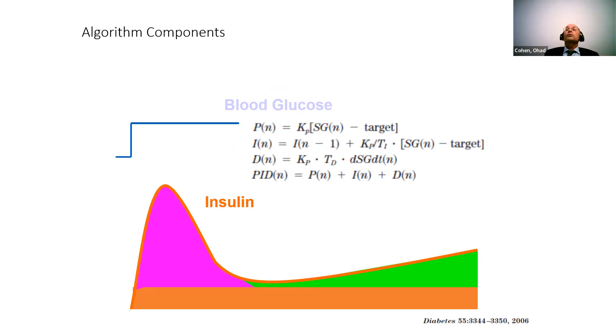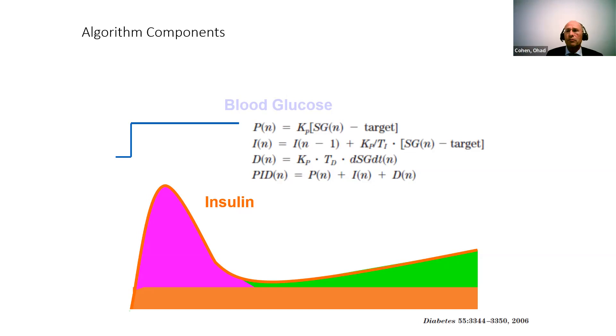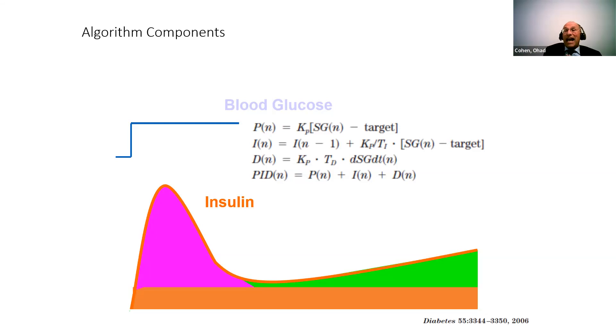The algorithm has many layers. The basic assumption is that when glucose goes from normal to a bit higher, calculations must consider: how far it is from target, how fast it's going up or down, and how long it has been in hyperglycemia. Each of these components affects the amount of insulin given. These three equations form what's called the PID — proportional, integral, and derivative — aspects of basal insulin secretion, producing a solution that really imitates physiology.